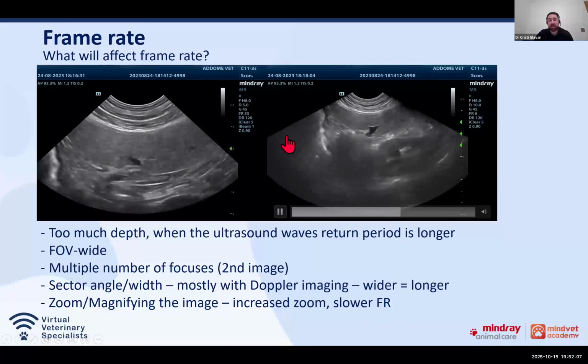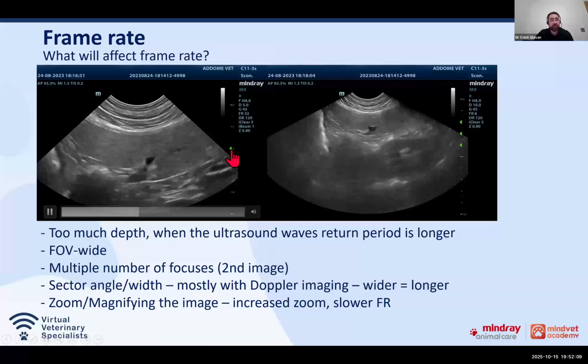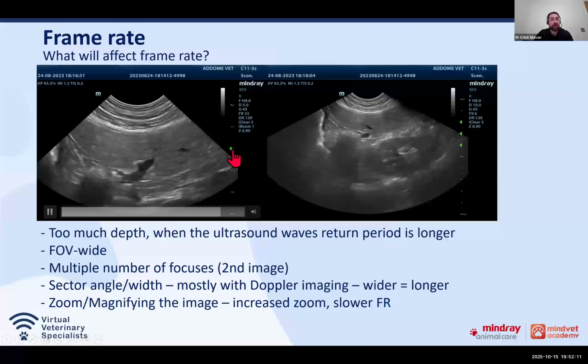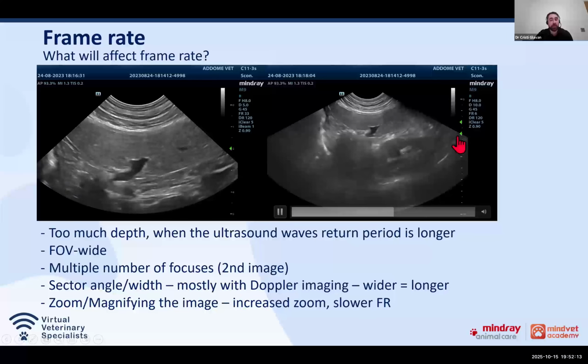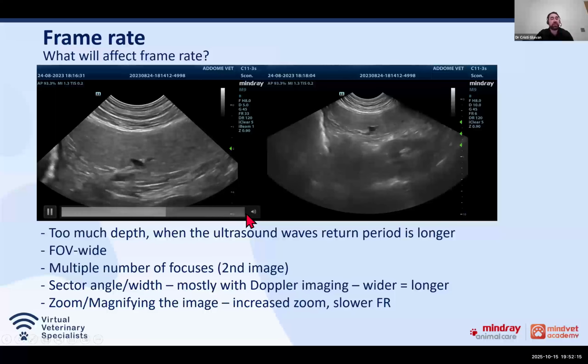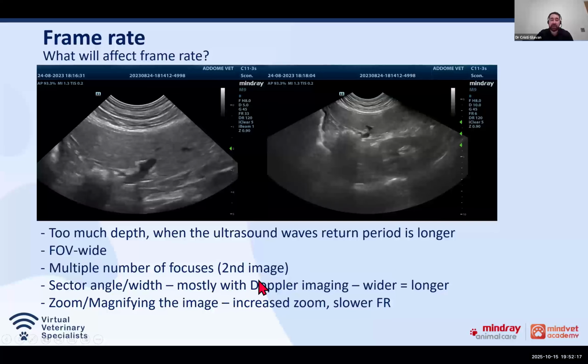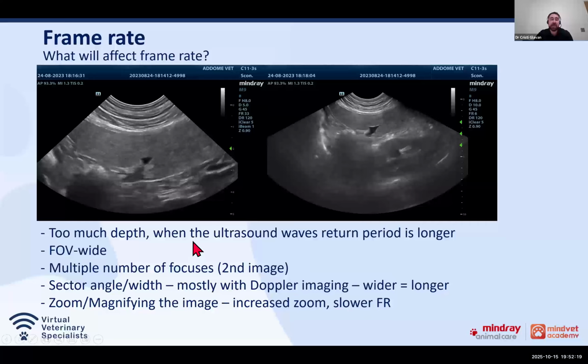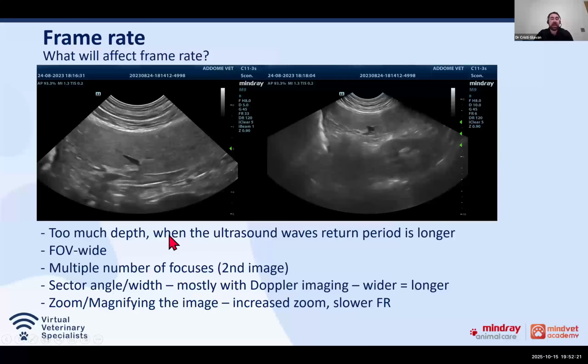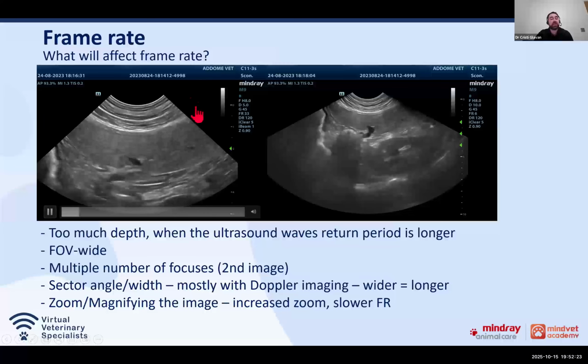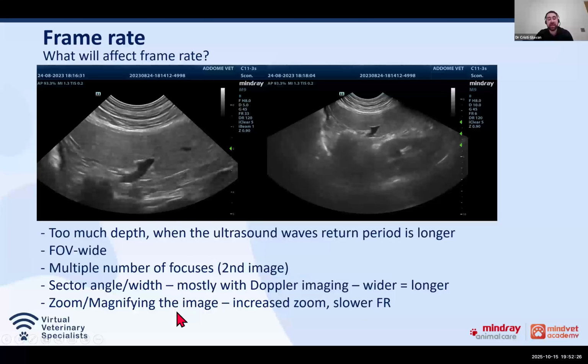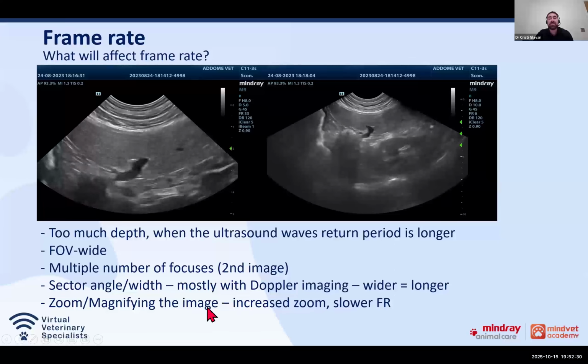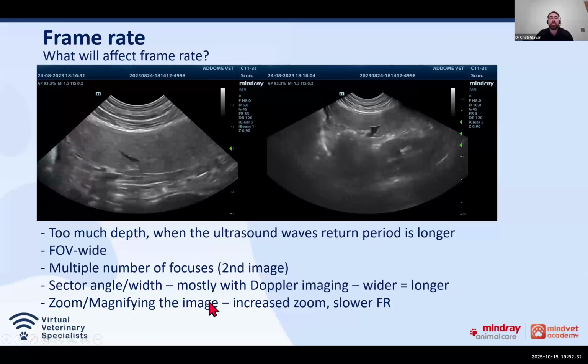And if you see here the difference between the focal point, we'll have one focal point and we'll have 3 focal points here. So usually the frame rate will be affected by multiple factors. If we have too much depth, so this means that if we are telling the ultrasound machine to scan at 10 centimeters deep, obviously the frame rate will be a bit slower. The image will take longer to be shown on the screen.